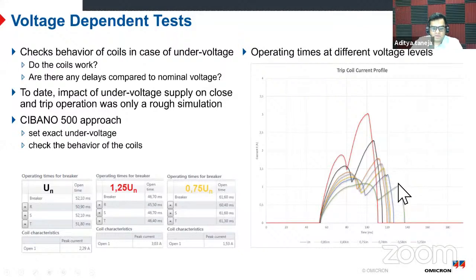And then we could see that the breaker timing really depends on this coil current. And in some cases, some coils failed to operate in under voltage condition, which should not be the case. So they were out of their design specs and needed to be replaced. So that's a much easier way to find problems. And you don't have to do anything else. You just need to change the voltage at which you are operating it.